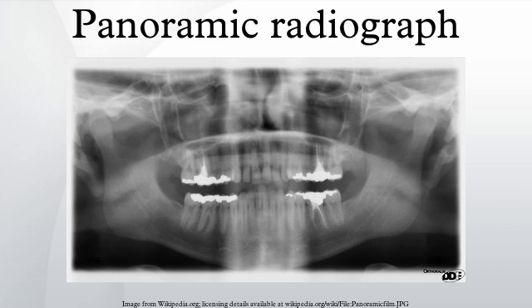Sometimes the term digital X-rays is used to designate scanned film documents handled by computers. Other types of digital imaging technologies use electronic sensors; a majority first convert the X-rays into light, which is further captured using a CCD or CMOS image sensor. Some use a hybrid analog-to-digital arrangement which first converts the X-ray into electricity, then rendered as an image using CMOS technology. In current state-of-the-art digital systems, image quality is vastly superior to conventional film-based systems, and the latest advancements have added cone beam 3D technology to standard digital panoramic devices.